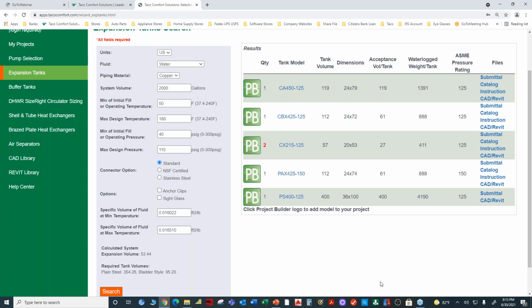Before we go into the selection on the right, let me point out a couple quick things with my pen. If you'll notice, the system calculated the fluid expansion. It said that under these conditions of 2,000 gallons, an initial temperature of 50 degrees Fahrenheit, and a final temperature of 180 degrees Fahrenheit, the water will expand approximately 53.44 gallons. It does give a little credit for copper, and I'll show you how that works in a minute.